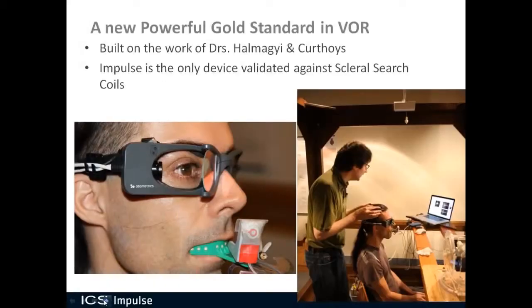ICS Impulse is bringing diagnostic accuracy and efficiency into balance testing. We want to make sure you perform the test properly so that you have accurate diagnostic results as well. The new powerful gold standard for vestibular ocular reflex, the ICS Impulse was built on the work of Drs. Halmagyi and Curthoys. Impulse is the only device validated against scleral search coils at the time of this video. You see the ICS Impulse goggles, the coil on the patient's eye, and the bite bar to measure the patient's head movement, with the full system set up to simultaneously collect coil data along with goggle data.